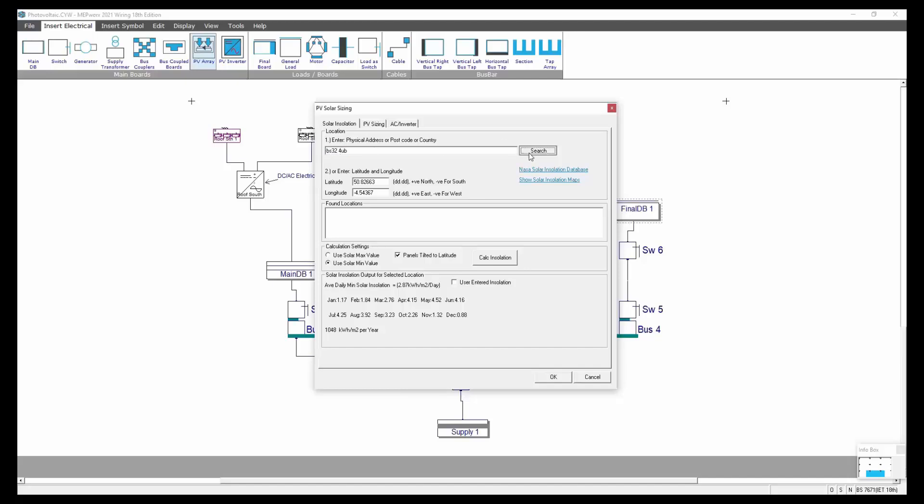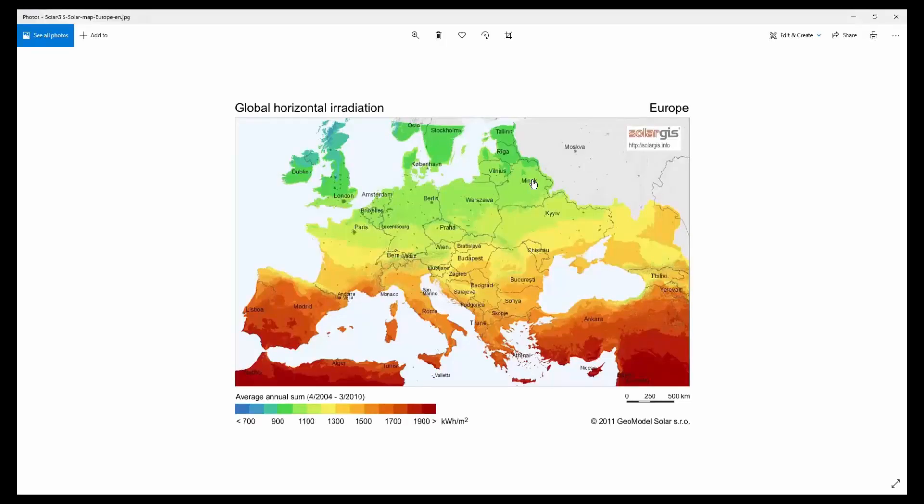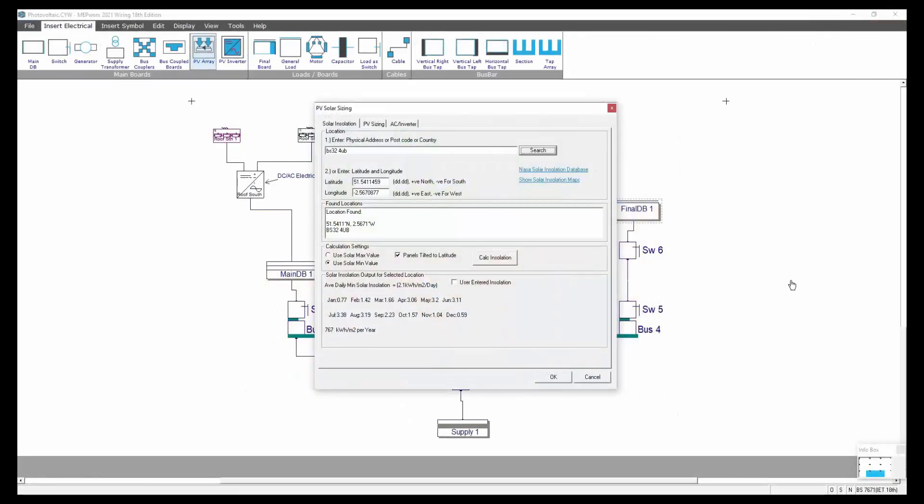If you're hooked online you can then do a search and that will find your location with a latitude and longitude. It uses the NASA GIS data set of over 260 locations in the UK to give you horizontal irradiance values. You can use minimum or maximum values, you can tilt the panels to latitude to get the maximum performance out of those panels.